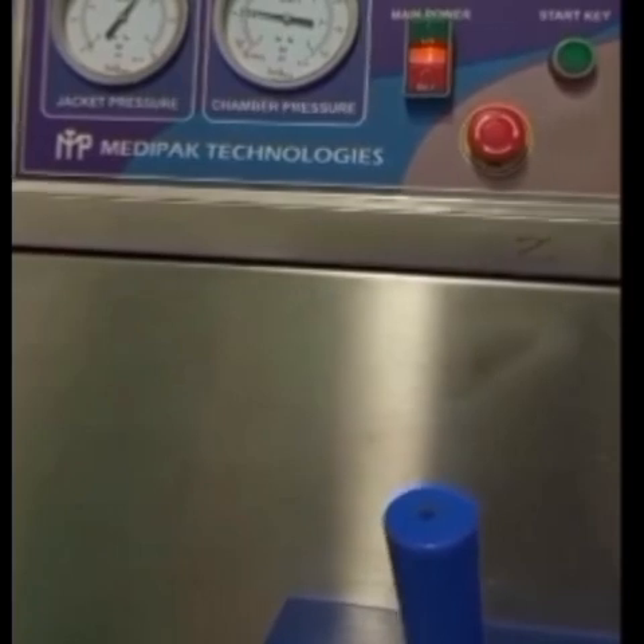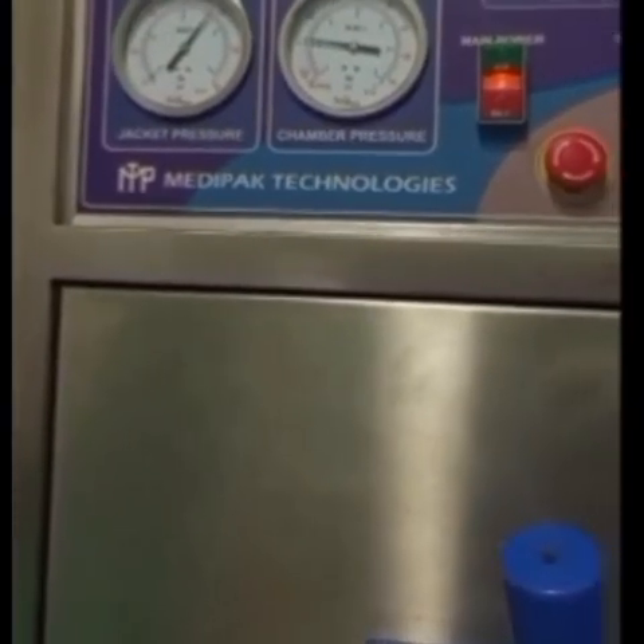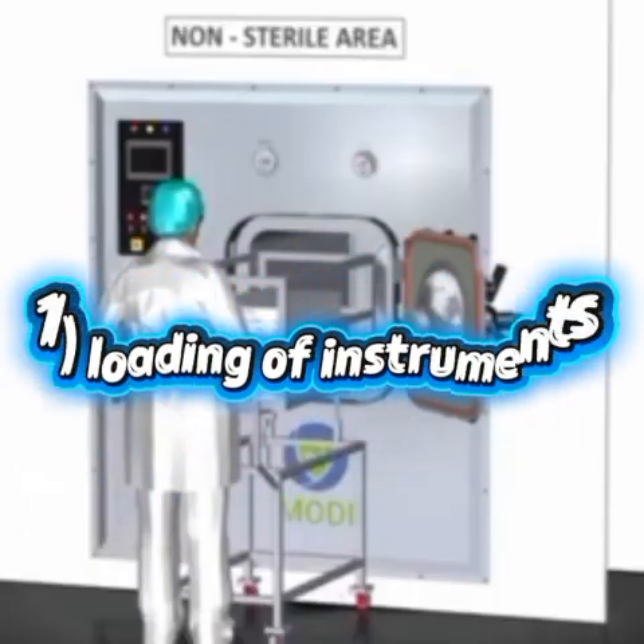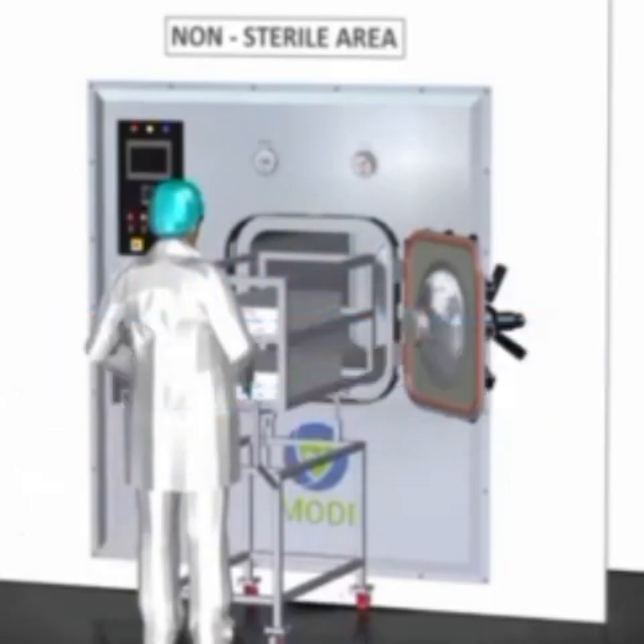Now, if we go through the detailed process, let me tell you the detailed process through points. First, loading of instruments. Before sterilization, instruments are properly cleaned, dried, and packed. They are then placed on stainless steel trays inside the autoclave chamber, ensuring proper spacing for steam circulation.